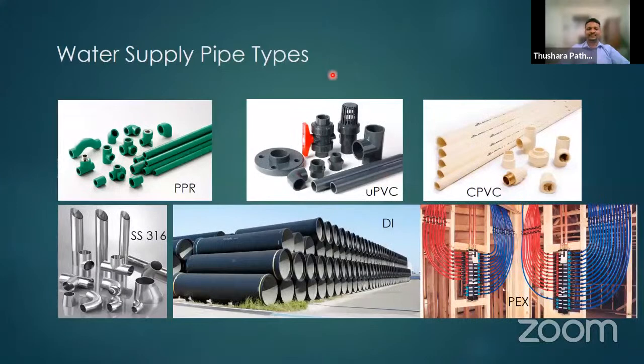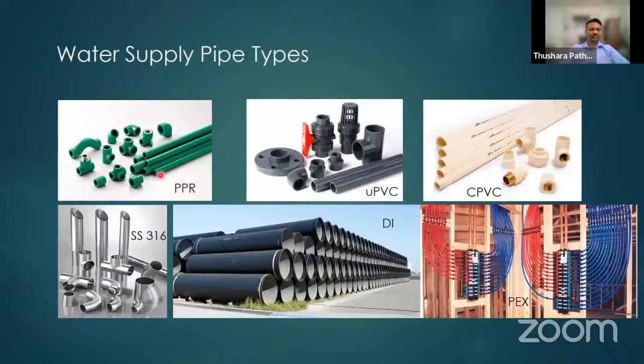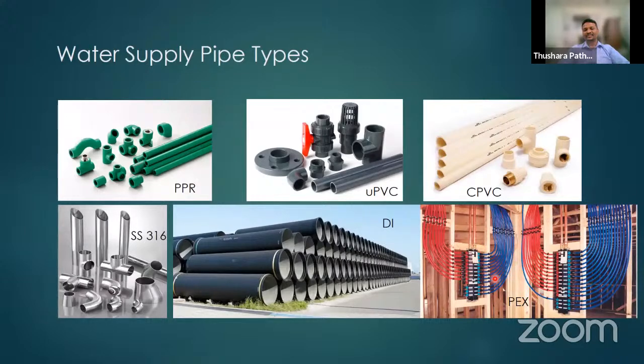There are many types of water supply pipes for both cold and hot water: PPR (polypropylene random) pipes for hot and cold water; uPVC generally for cold water; CPVC for both; SS316 stainless steel and ductile iron for cold water supply — mainly for municipal water supply systems; and PEX pipes, which are flexible pipes used in risers to connect sanitary appliances. These cover the main pipe types used in plumbing systems.